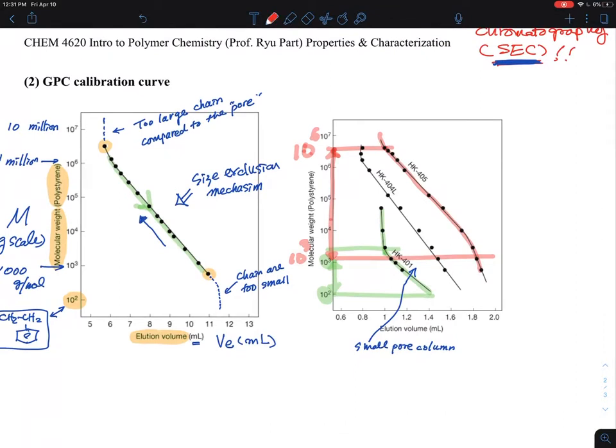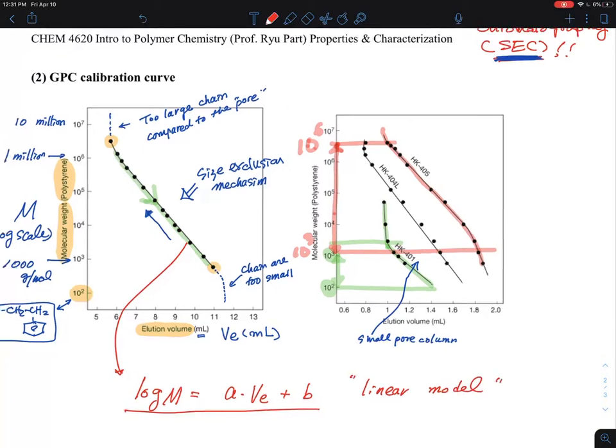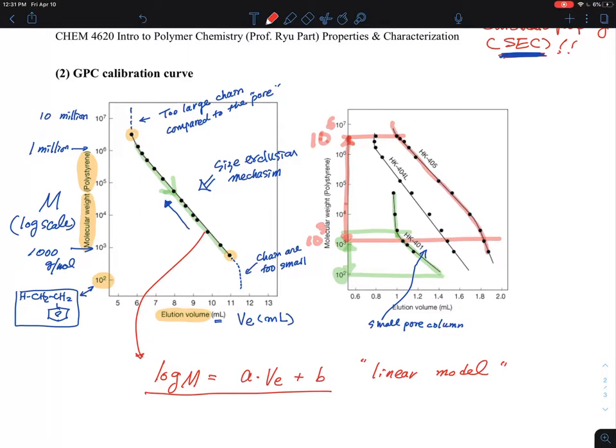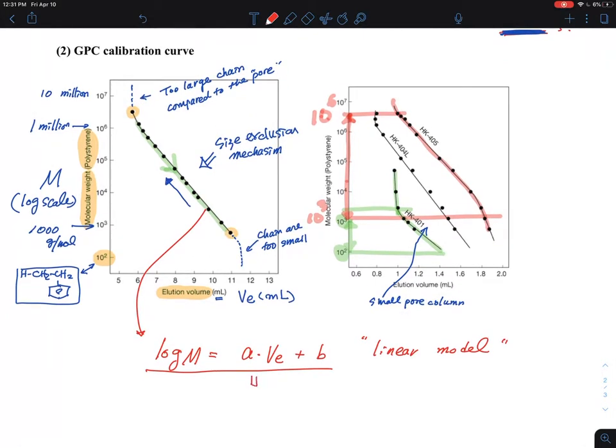And so if you go to this relationship, you can think about, okay, log molecular weight. In a very simple sense, it is A times elution volume with an offset B, right? This is a linear model. So you can have this calibration curve based on that. But people probably use a more cubic model, which is A·Ve³ + B·Ve² + C·Ve + D. This is a cubic model.